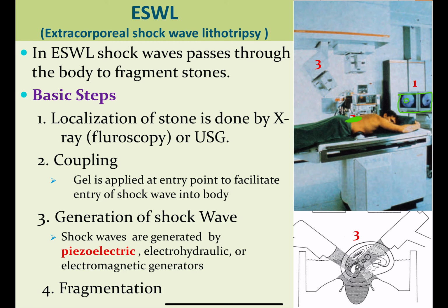So when you apply the gel at the entry point, now this machine, which is very focused, will produce a shock wave exactly at the point where we have targeted. Once it produces the shock wave, it will go inside exactly at the focused point and start breaking the stone into fragments. So this shock wave can be produced by various machines, but nowadays we use a piezoelectric technique where the ceramic plates vibrate to produce a shock wave. So piezoelectric shock waves are commonly used nowadays.